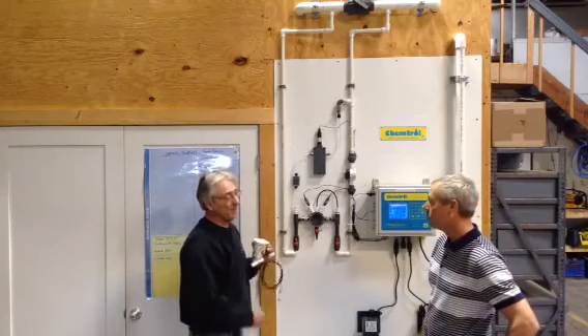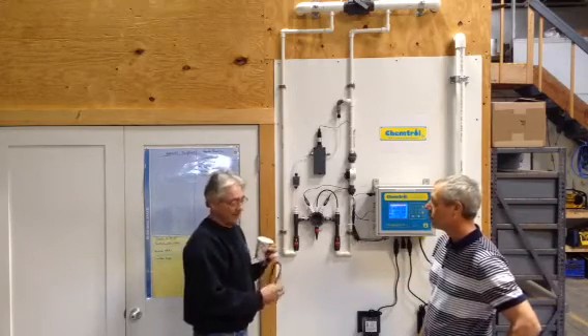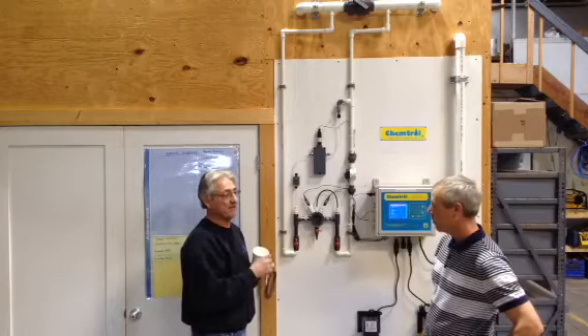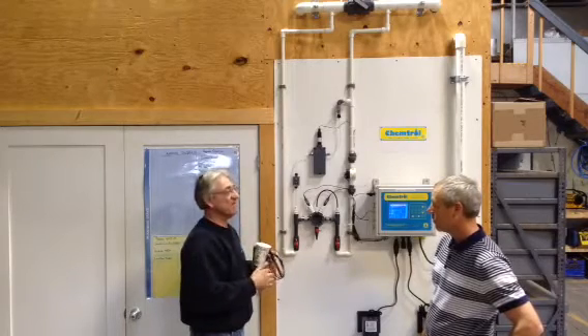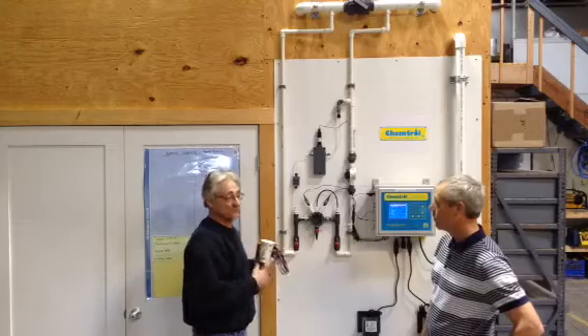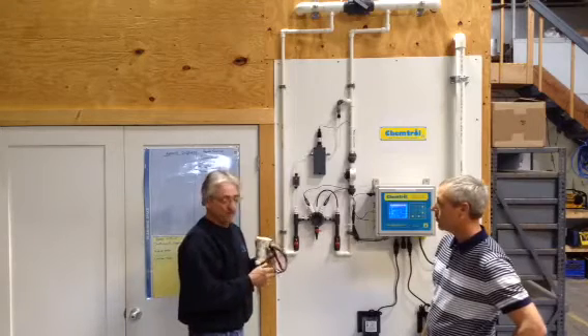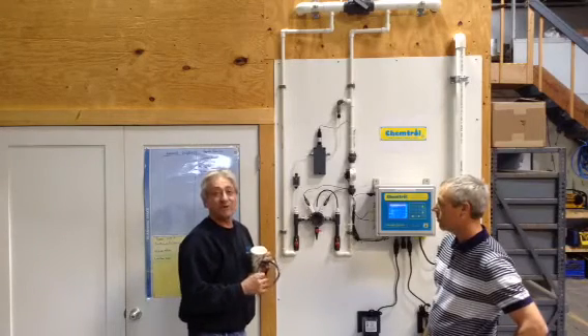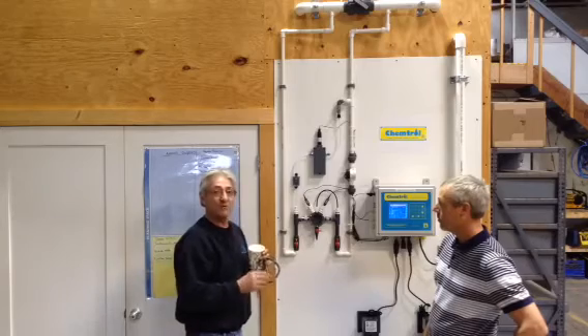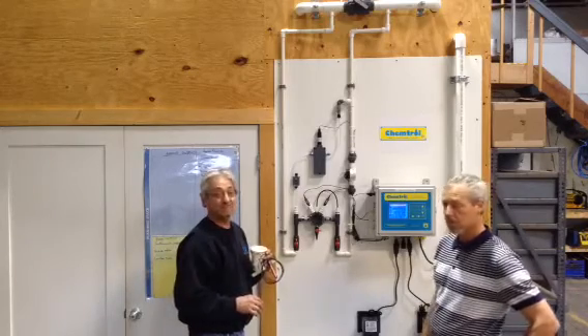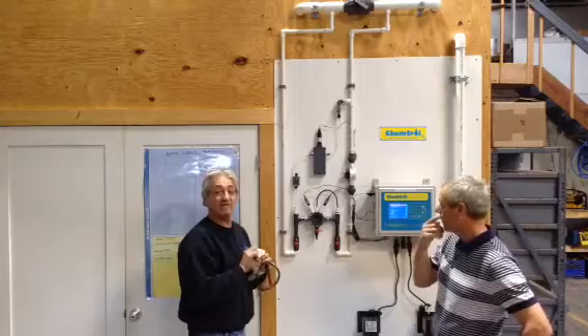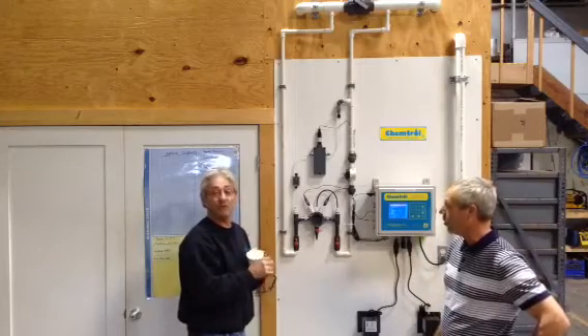We can also come out with a tester, and we can actually check the signal that these are getting, especially the pH probe. It'll tell us how far off it is from the true water coming by. We can put it into a sample of 7.5, and with a meter we can find out how bad the probes are. There's also a date code on every probe, so you can tell how old it was.